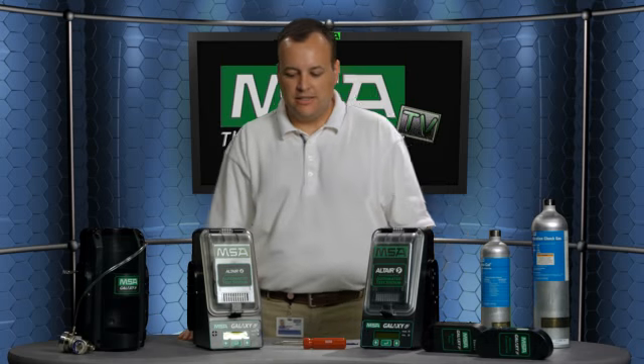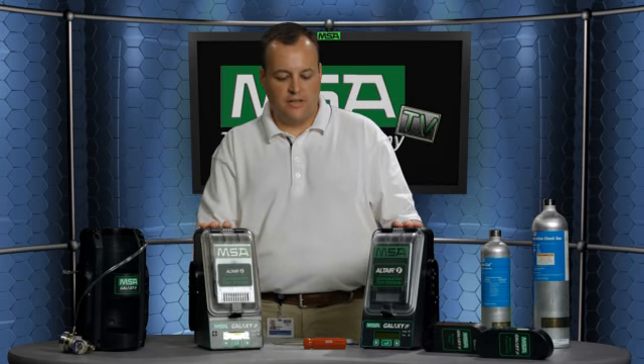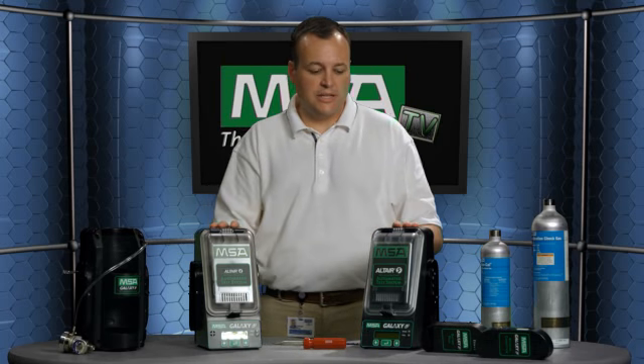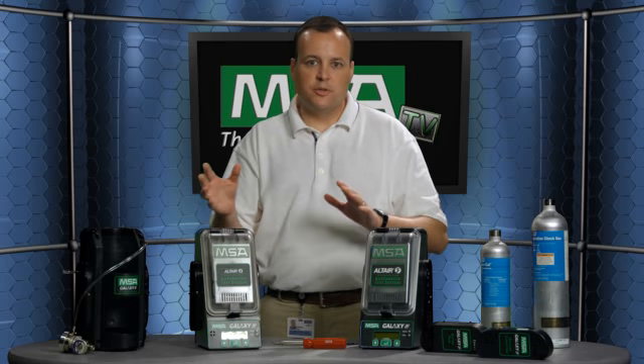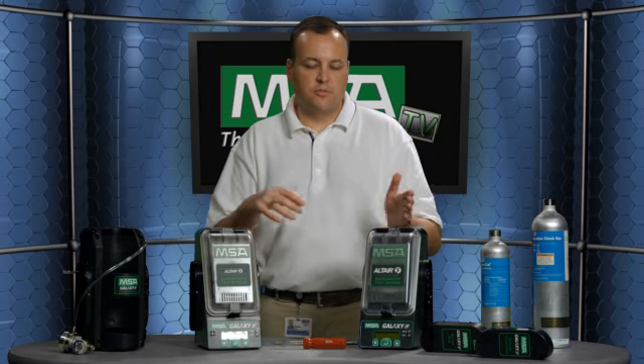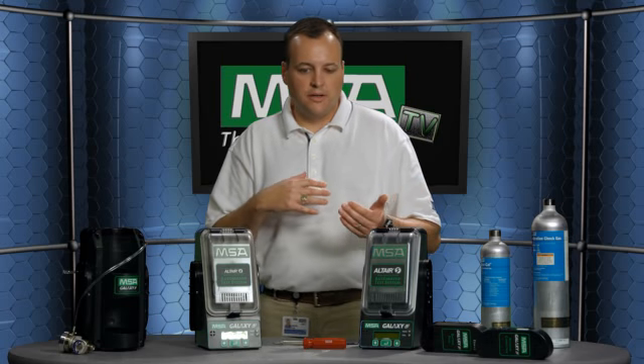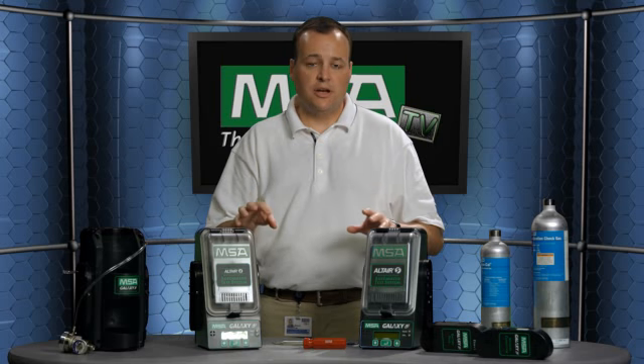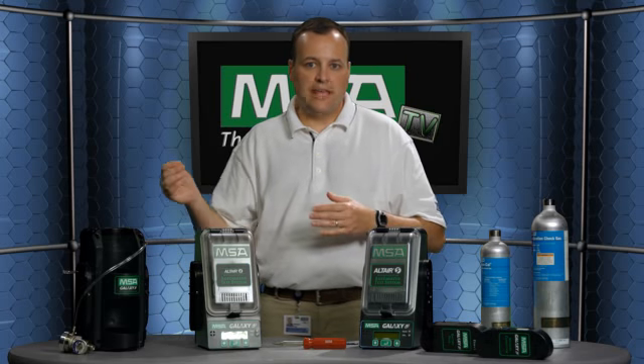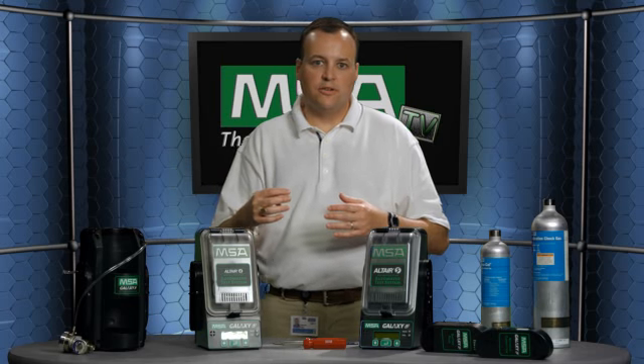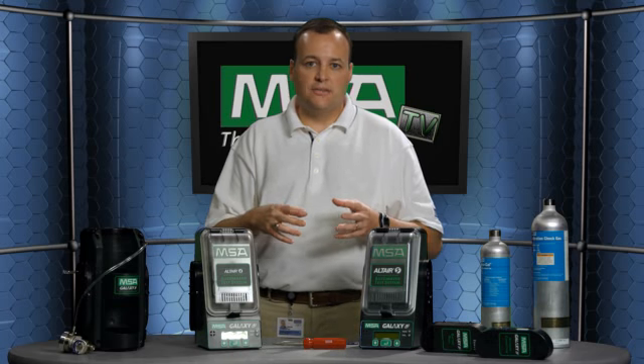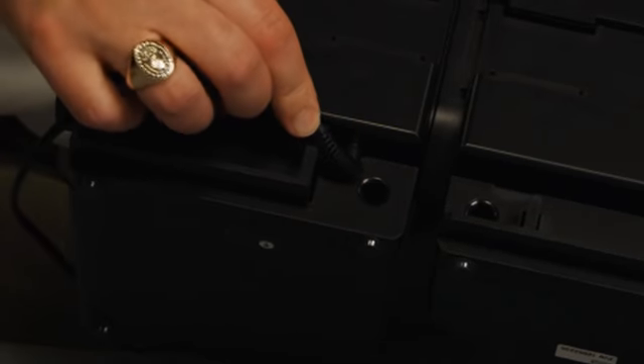An additional feature with the Galaxy automated calibration systems is that as you have, let's say, 10 of these test stations or stands hooked up together, in hooking up the different combination of instruments, what sets this system apart from the rest of the industry is that you can calibrate multiple instruments at the same time, so that if you put 10 instruments into 10 test stations at the same time, they will all start calibrating at the same time. There's enough gas flow through the system in the way that our internal plumbing is designed to allow for that to occur. Some other units out in the industry, as you put in the first unit, that would calibrate or bump, go all the way through to finish until the second, the third, the fourth, and the fifth, sixth, seventh, eighth would start in sequence.